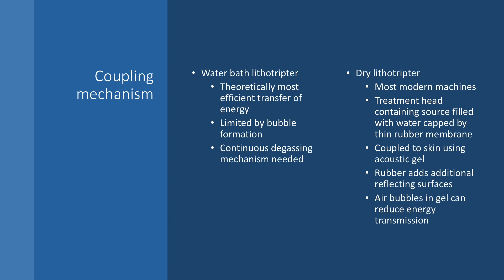There are two main types of coupling mechanism. Earlier lithotriptors, such as the EHL model Dornier HM3, relied on a water bath coupling mechanism. This is theoretically the most efficient type of coupling, as the shockwave is generated and conducted by the water directly to the patient's skin, resulting in transmission of almost all the energy into the patient. However, the energy is limited by bubble formation within the water bath, and therefore this kind of lithotriptor had a continuous degassing mechanism installed to try and remove air bubbles as they are generated.